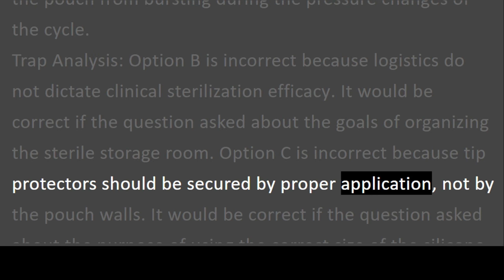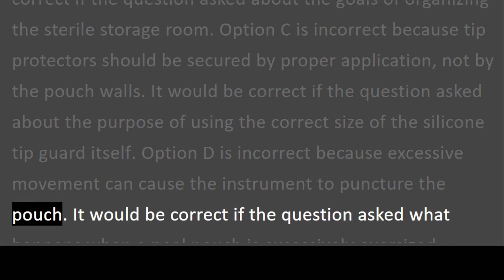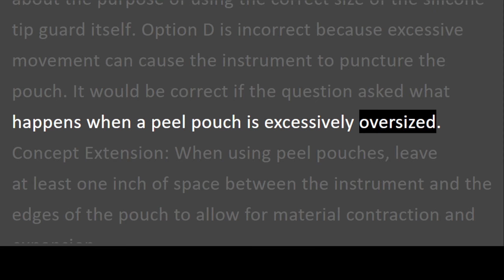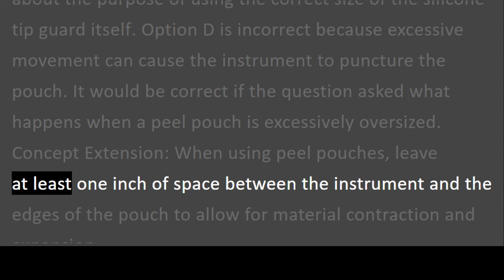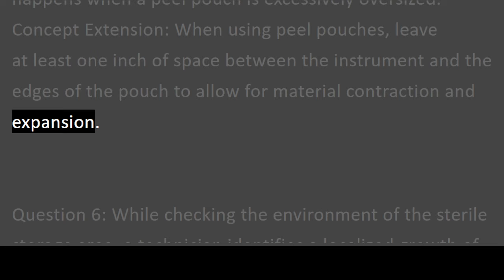Option C is incorrect because tip protectors should be secured by proper application, not by the pouch walls. It would be correct if the question asked about the purpose of using the correct size of the silicone tip guard itself. Option D is incorrect because excessive movement can cause the instrument to puncture the pouch. It would be correct if the question asked what happens when a peel pouch is excessively oversized. Concept extension. When using peel pouches, leave at least 1 inch of space between the instrument and the edges of the pouch to allow for material contraction and expansion.